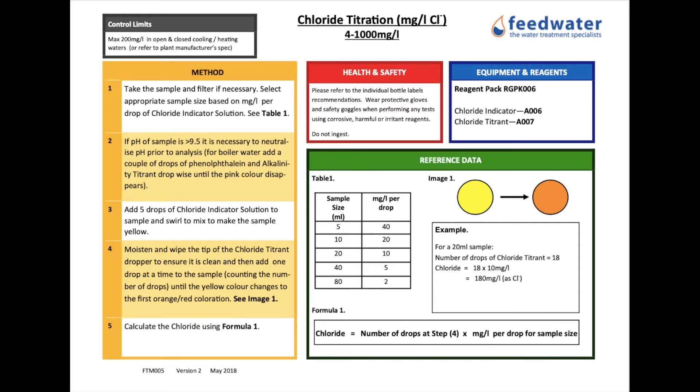This method can be used for chloride measurement in open and closed cooling and heating waters and boilers. The range for this method is 4-1000mg per litre. The control limits for chloride are a maximum of 200mg per litre in open and closed cooling and heating waters or refer to the plant manufacturer's specification.